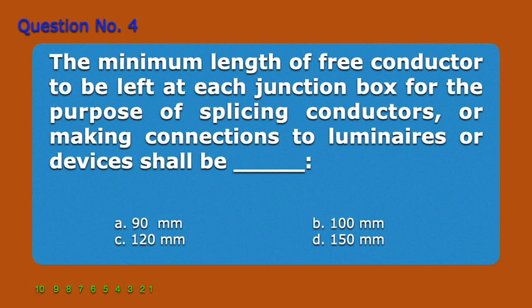Question number 4. The minimum length of free conductor to be left at each junction box for the purpose of splicing conductors or making connections to luminaires or devices shall be blank. A. 90 mm. B. 100 mm. C. 120 mm. D. 150 mm.